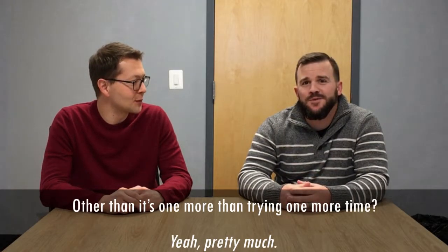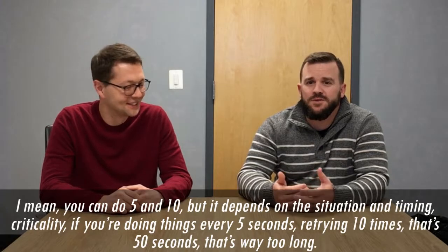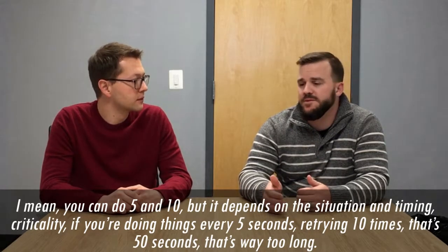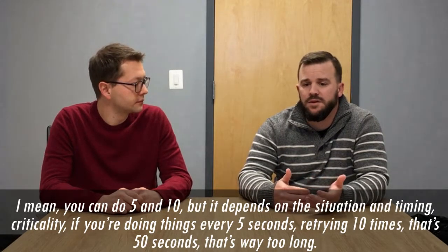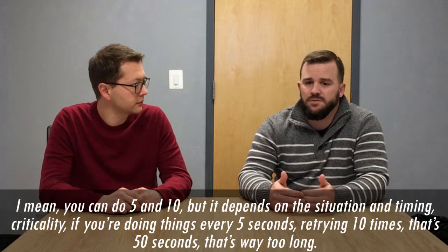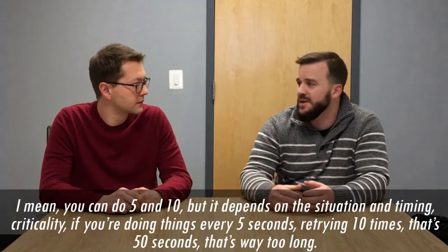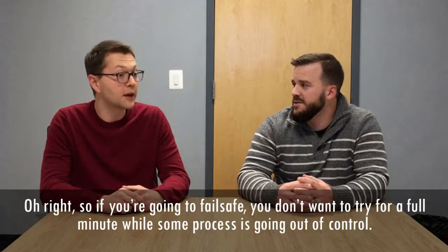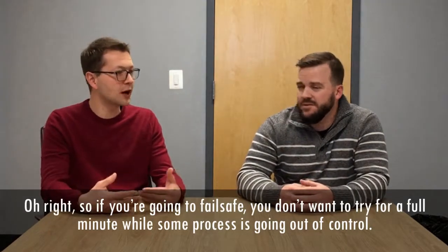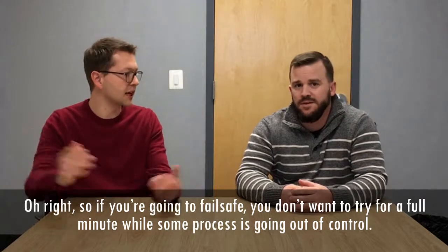Other than it's one more than trying one more time? Yeah, pretty much. I mean, you can do 5 and 10, but it depends on the situation and timing, criticality. If you're doing things every 5 seconds, retrying 10 times, that's 50 seconds. That's way too long. Oh, right. So if you're going to fail safe, you don't want to try for a full minute while some process is going out of control.